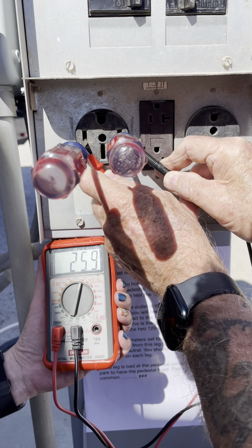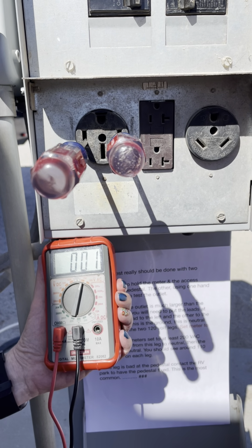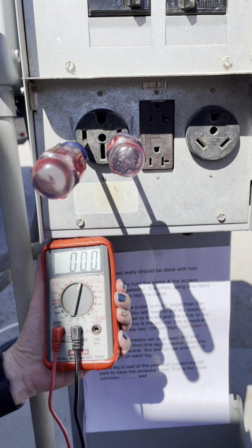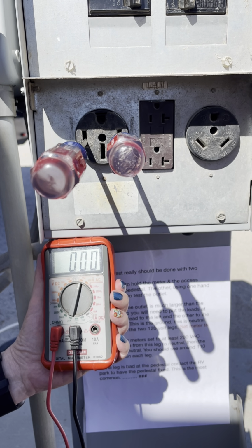So we got 259 volts. That is excellent. So we now know that both legs are good. If one leg is bad, be sure to contact the RV park and have the pedestal fixed. This is the most common failure. Depending on what happened inside, if you did not have power inside the coach, but you had power at the pedestal, that means you're losing power somewhere between the pedestal and the main circuit breaker.